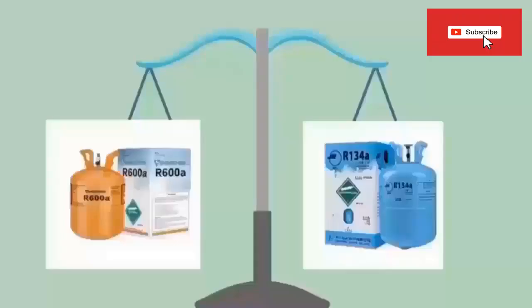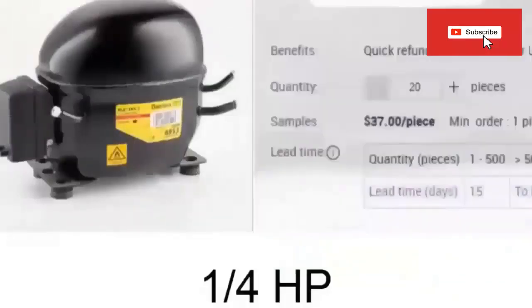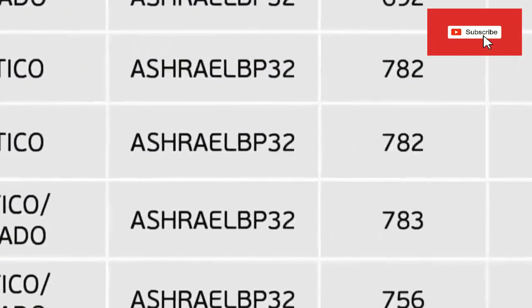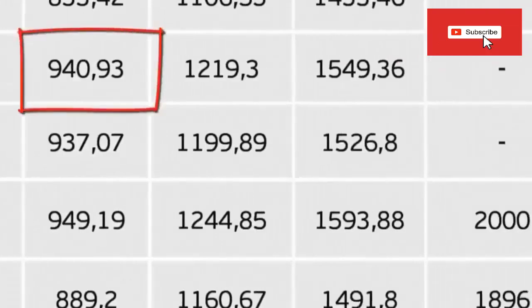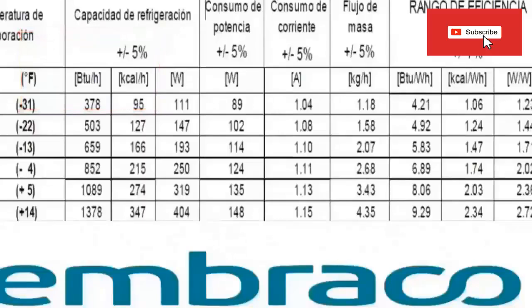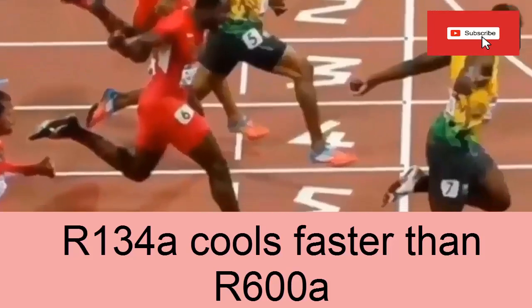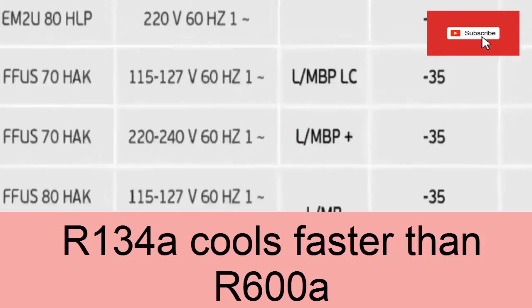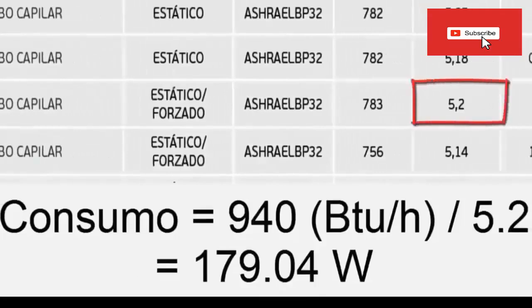Now we are going to compare compressors with R600a against compressors that work with R134A, starting with a typical quarter HP compressor used in domestic refrigerators. For R134A, using the Embraco catalog, for a refrigerator that works at minus 20 degrees Celsius, the cooling capacity this compressor can achieve is 940 BTU per hour. For R600a, the compressor can reach a cooling capacity of 852 BTU per hour. This means the R134A compressor, having greater cooling capacity, would reach the low temperature faster. The electrical consumption for the R134A compressor is close to 179.04 W, calculated with the energy efficiency factor in the table.